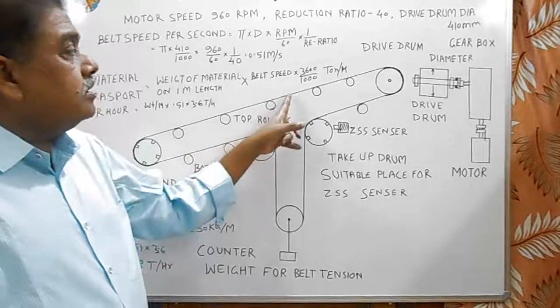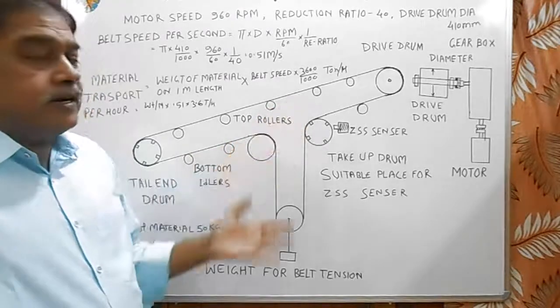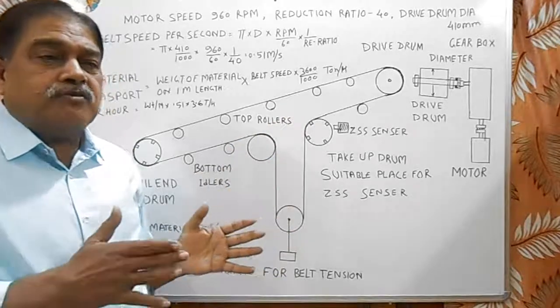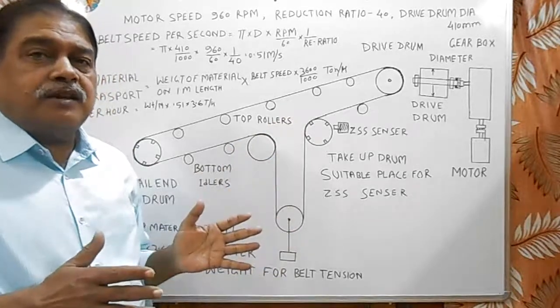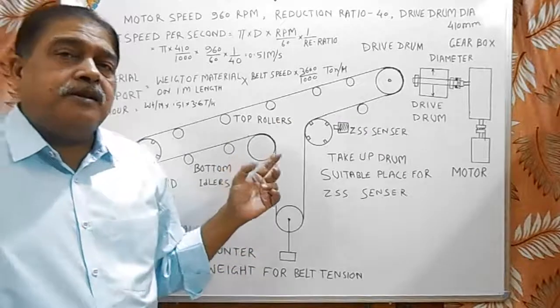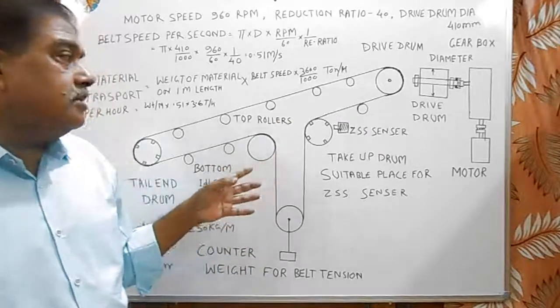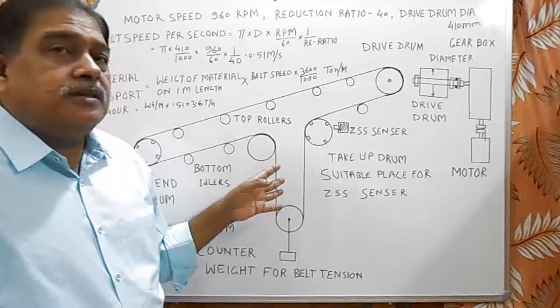In addition to that, belt sway switches are provided on both sides of the belt conveyor. So if belt sways to any side of the center, then the belt switch operates and belt stops. And this way stops the spillage of material.